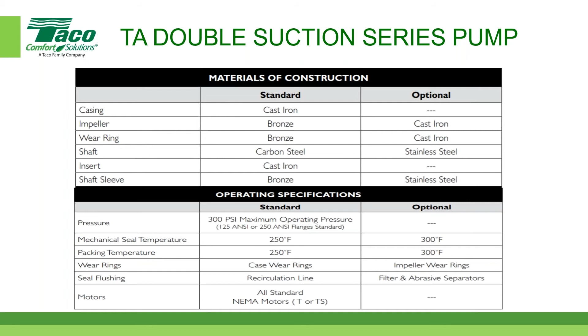So here's a cutaway of a double suction, horizontal double suction pump. When we talk about the water, these are the chambers here. There's that flush line I talked about, and I have a couple other sketches that'll show you even more callout of different components. The suction and discharge is down below here, but you can see the water goes into both sides of the impeller. We'll talk about the piping and the flow rates to make sure we understand that as well.